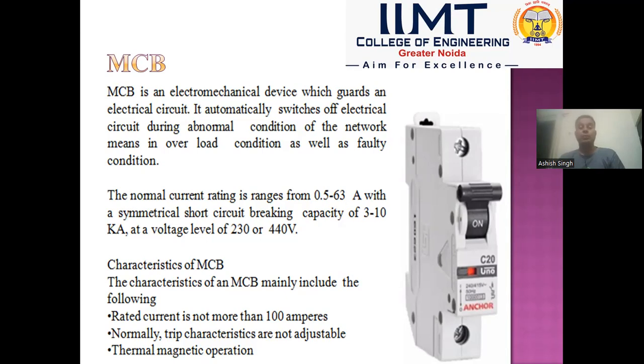In case of MCB, rated current is not more than 100 amperes. Normally, trip characteristics are non-adjustable in MCB. That means we cannot adjust the tripping current as per our requirement. And it operates basically either thermally or magnetically. During faulty condition, when an excessive amount of current is flowing through the circuit, then MCB operates using the magnetic effect of current.